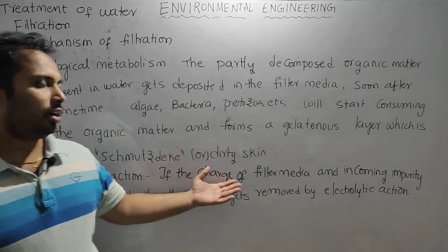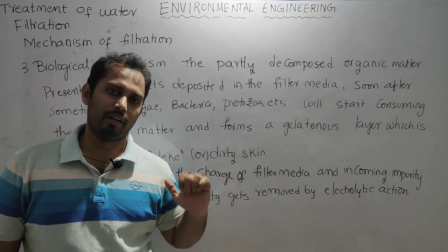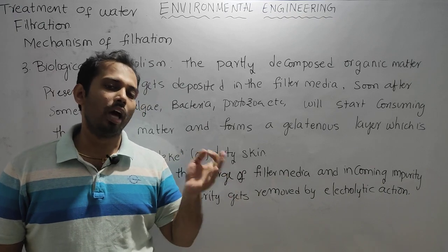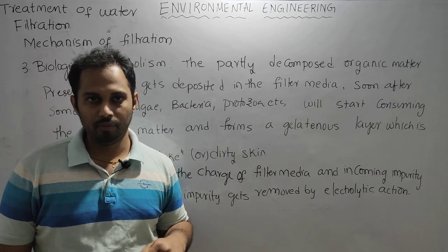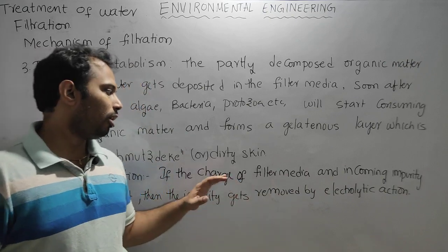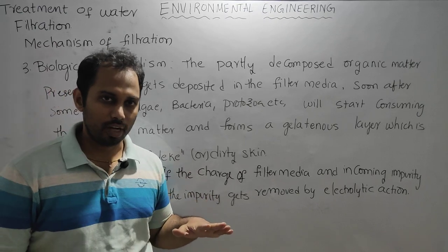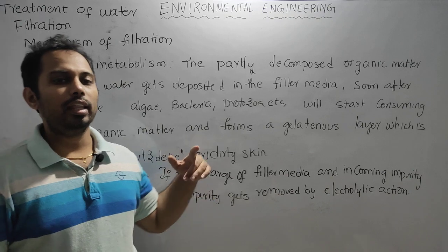But there is a limit to this charge transfer, because the charge of the filter media is fixed. If the complete charge is exhausted by the incoming oppositely charged impurities, at some point the filter media loses its capability of charge neutralization. At that point we need to do maintenance, otherwise it will not have any more electrolytic action removal capacity.